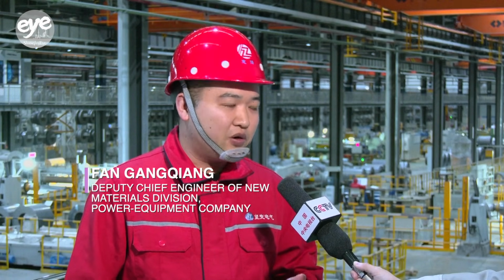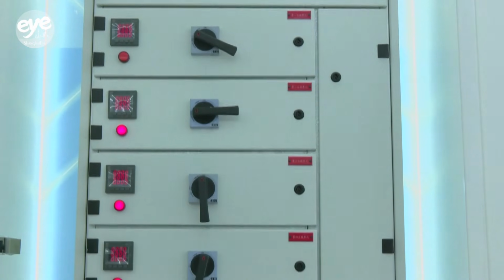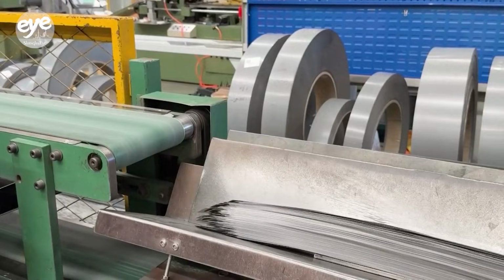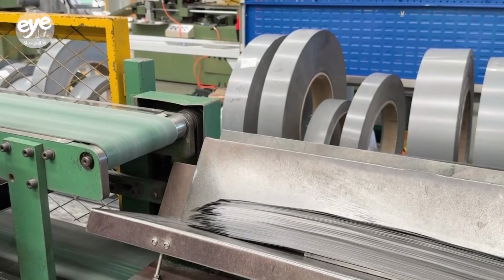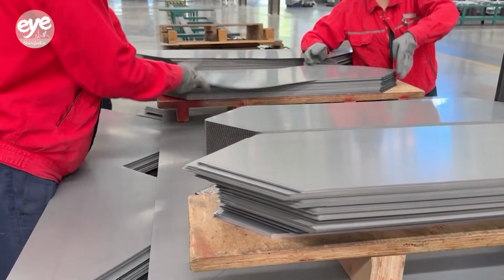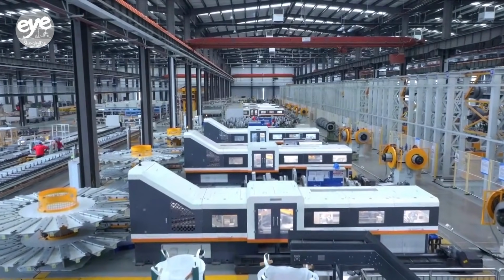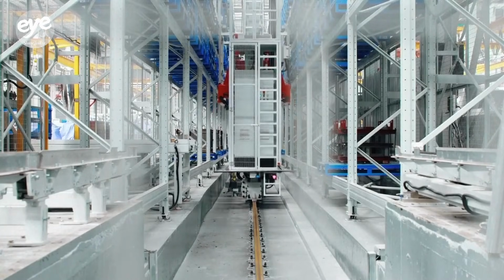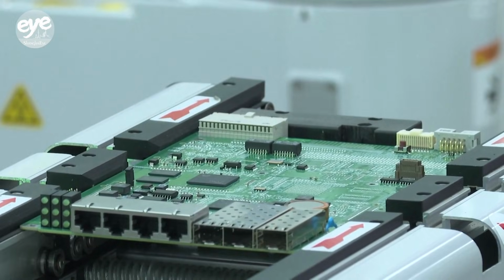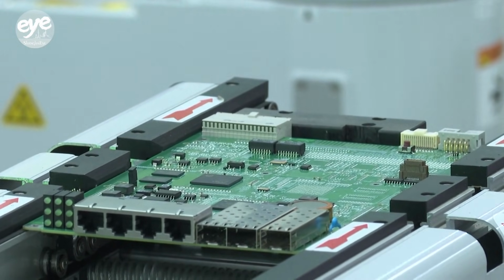We recently developed thinner products of 0.2 millimeters or below. They offer higher magnetic induction and significantly lower iron loss. When used in transformers, energy loss can be reduced by roughly 20%. For a transformer weighing about 200 tons, that translates into annual electricity savings of roughly 400,000 to 500,000 kilowatt hours.